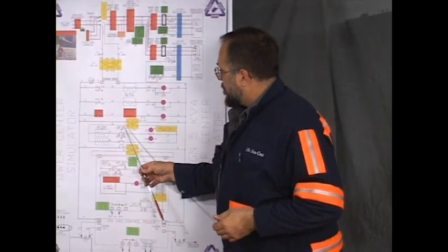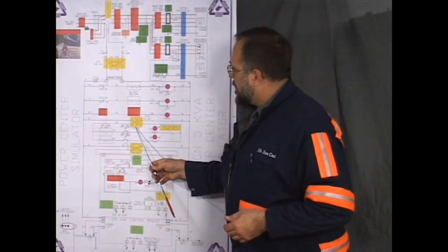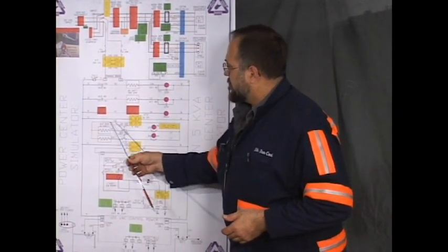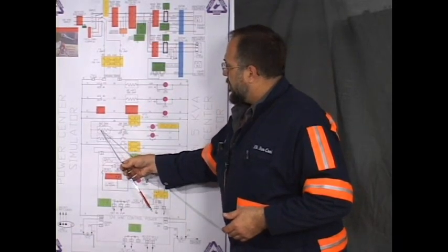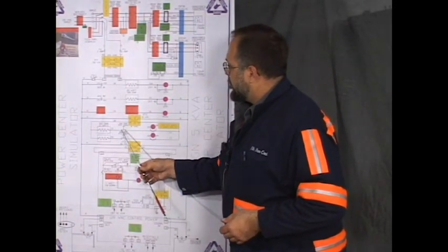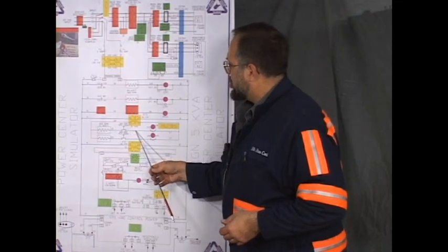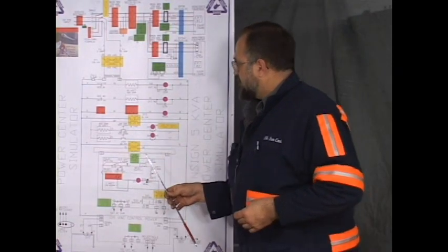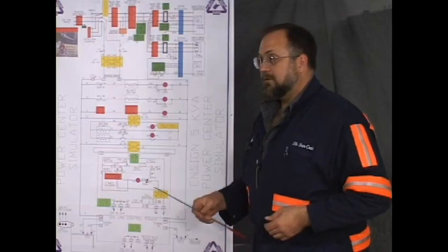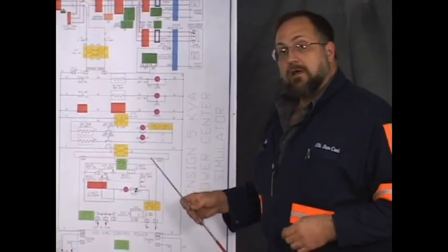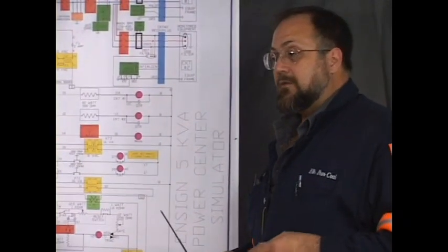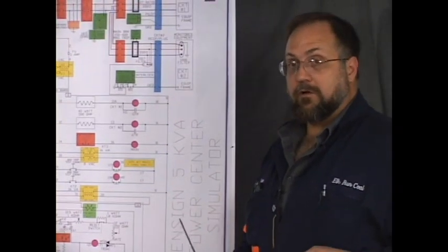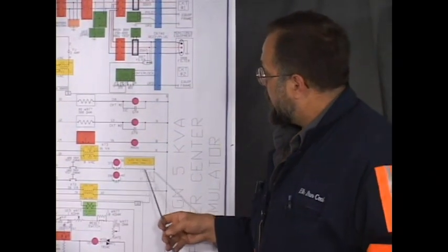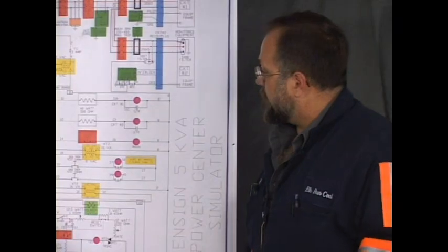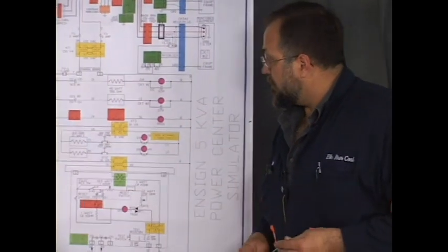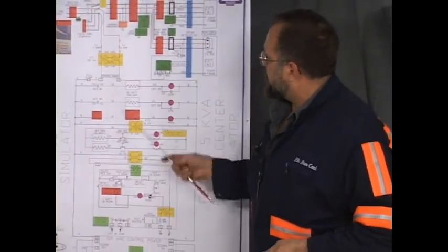This wire has a small voltage applied, 8 volts AC, passing through an 8.2 ohm resistor. When you depress this switch, it energizes this wire, 17. 17 passes through the CT 7 times. It's looped 7 times, and by looping it 7 times, you multiply its current 7 times, and then it returns to the control transformer. The resistor is here for the same purpose this resistor is.